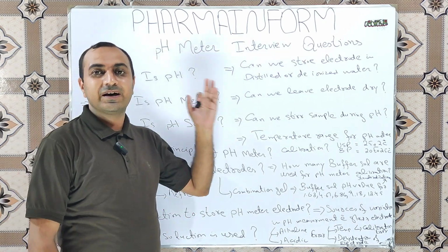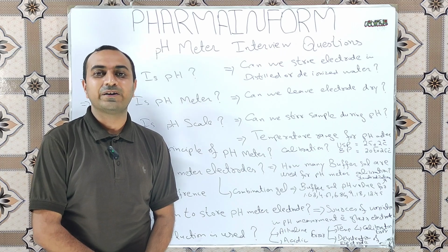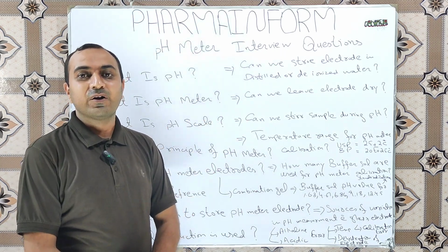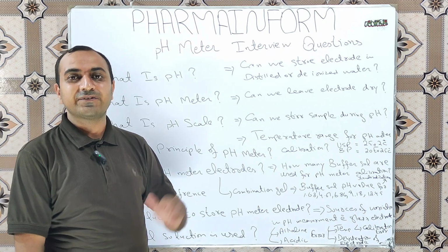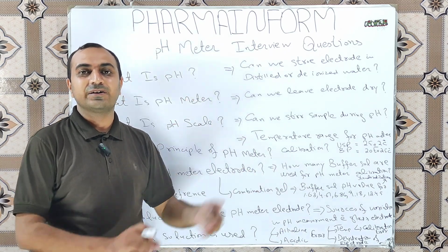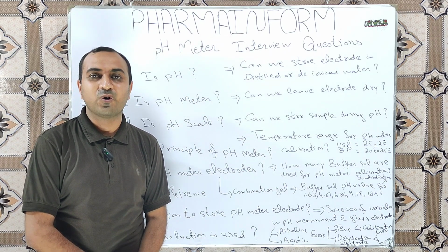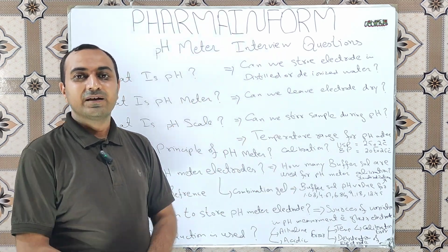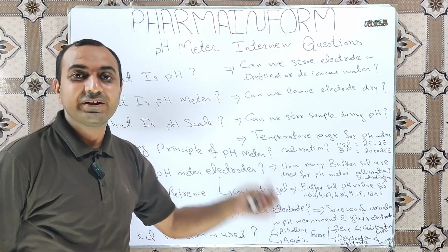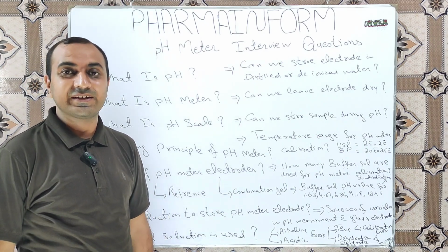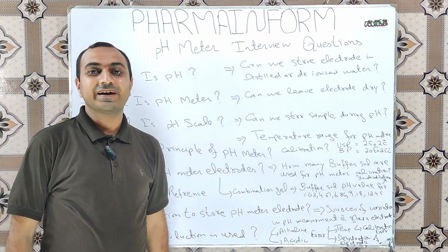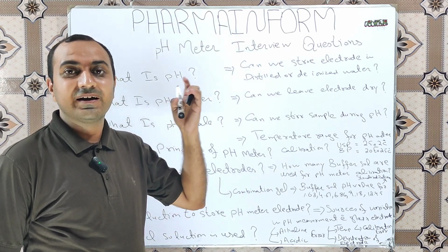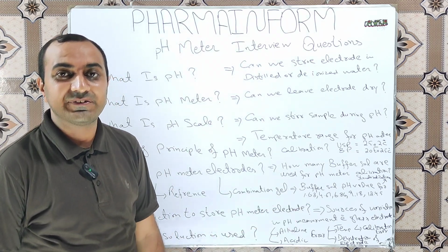In the pH meter, the electric potential is measured by using two electrodes to create an electric circuit. One of these electrodes is known as a reference electrode, and it contains a substance of known electric potential, and the other electrode, known as the sensor electrode, is inserted into the solution being tested. Electric potential is the difference that results from comparing the reference electrode to the sensor electrode.